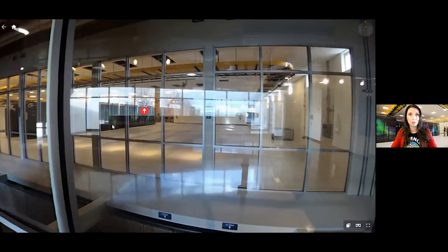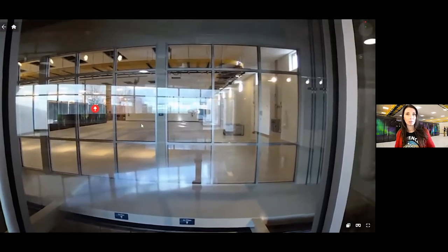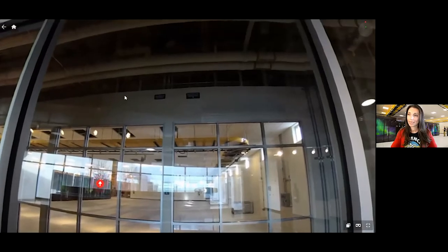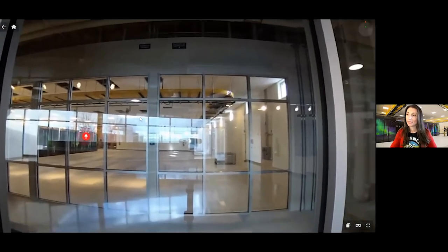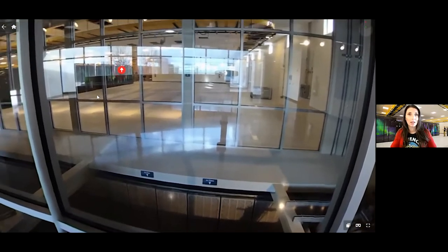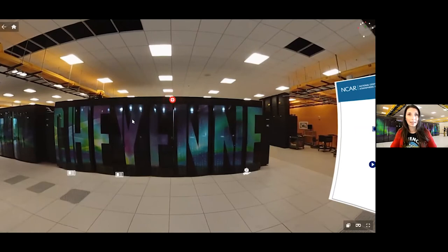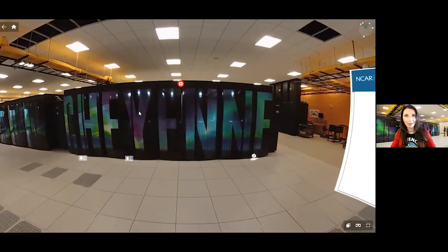All of the heat from the supercomputer, servers, and network storage rises up into the ceiling corridor, where it's cooled and humidified — humidified because Wyoming's climate is a little dry. That warm air comes down into a corridor and through a filter wall. Behind the filter wall is a huge fan wall that pulls that warm air through, cools it, and it comes back up through grated slots in the data center floor. That's what keeps our costs down.